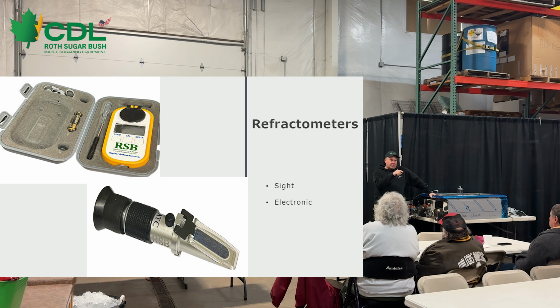Okay, if I hit that button 3 times and I get the exact same reading 3 times in a row, I know that is my reading. If I put a drop on there and I don't wait for it and I hit go, sometimes I'll get a reading that'll be 1/10, 2/10, or even 3/10 of a brix different. So we need to make sure whichever device we're using, give it just a minute, let the syrup and the lens become the same temperature before making that reading so that we're getting the most accurate reading that we can. So is anybody using refractometers at all?